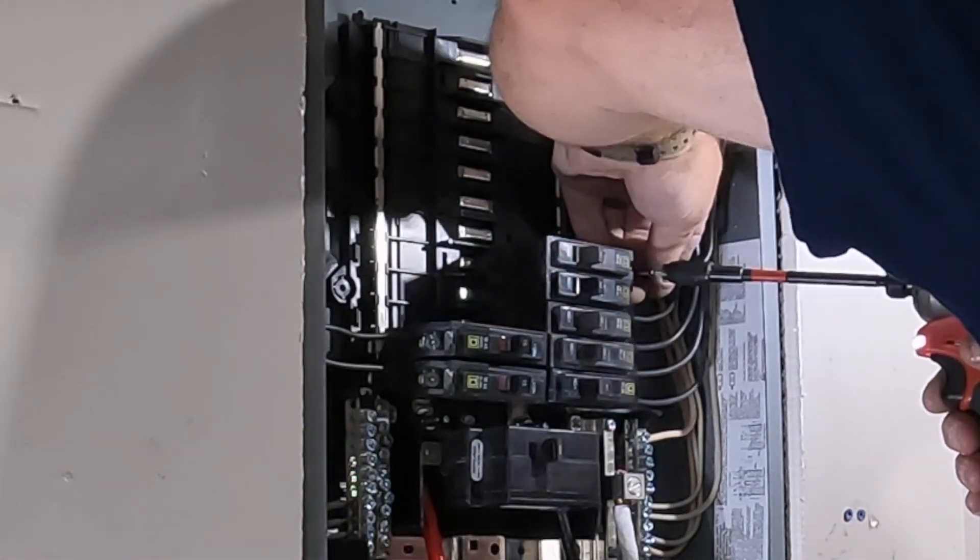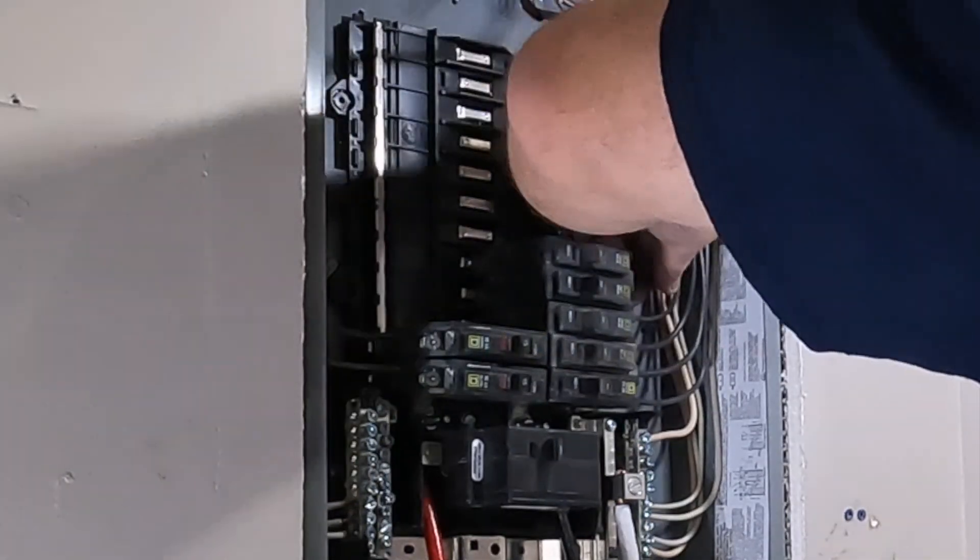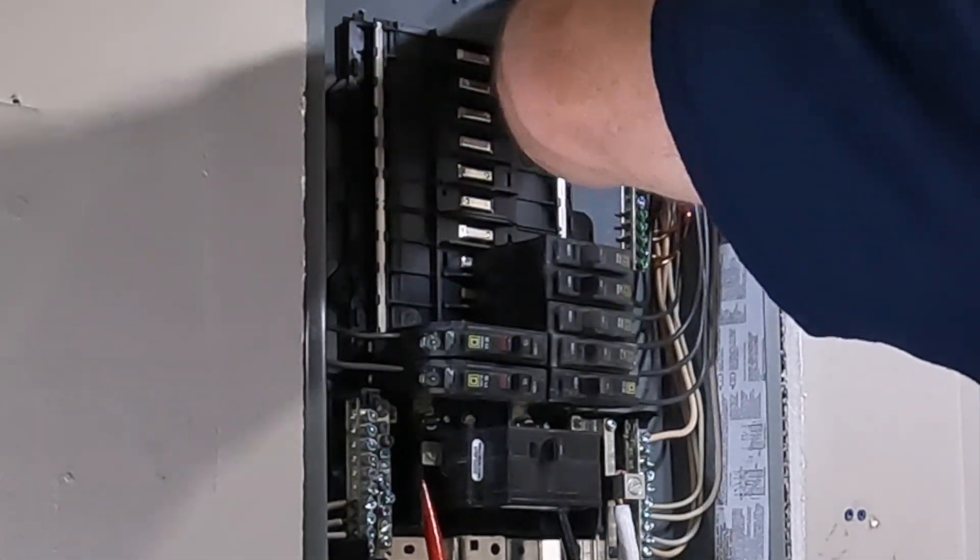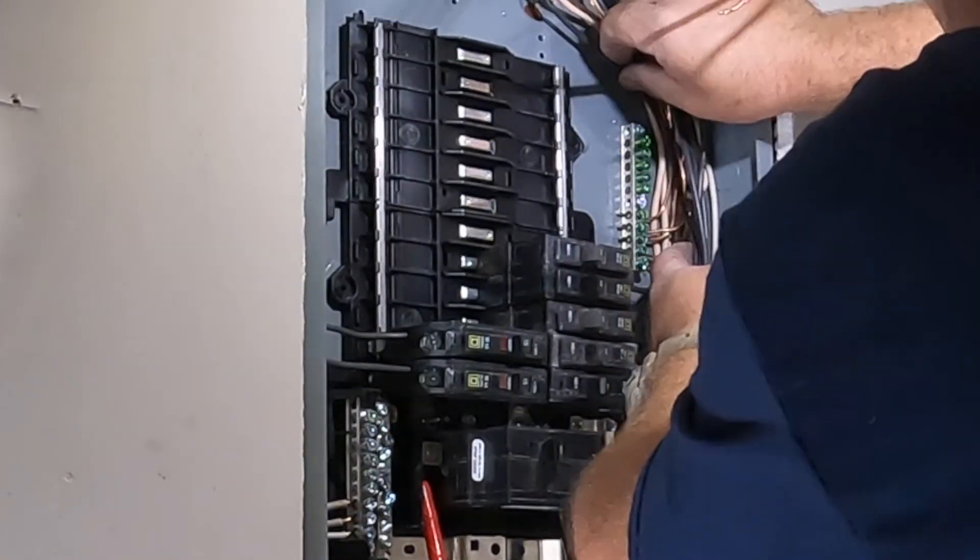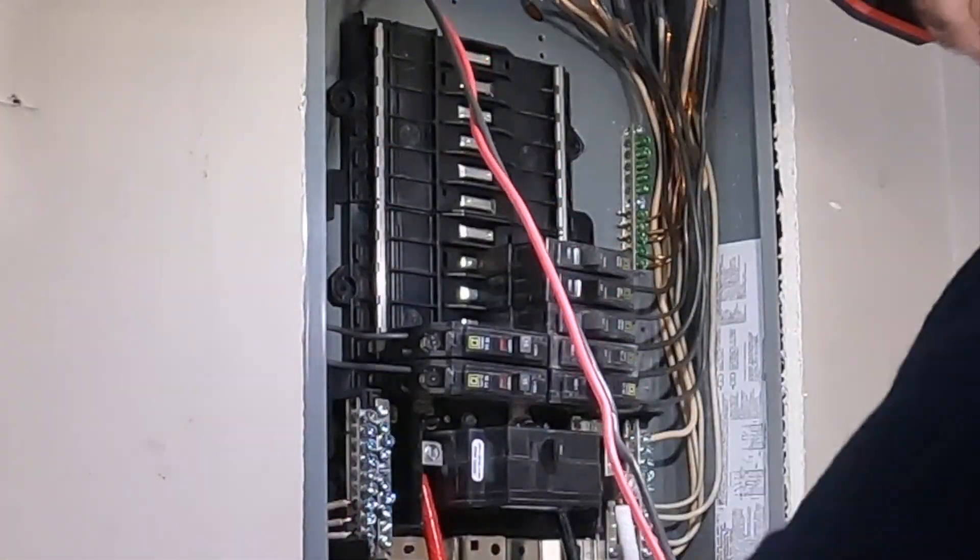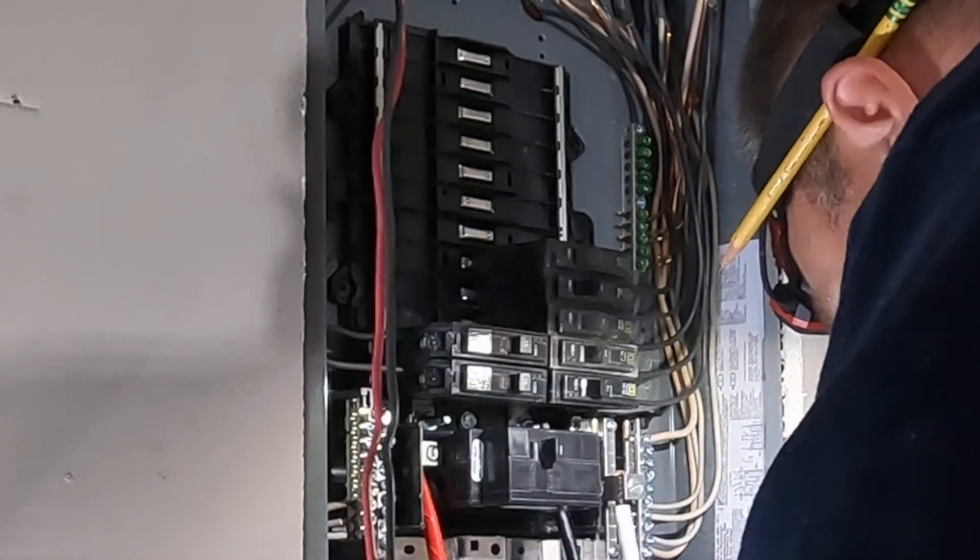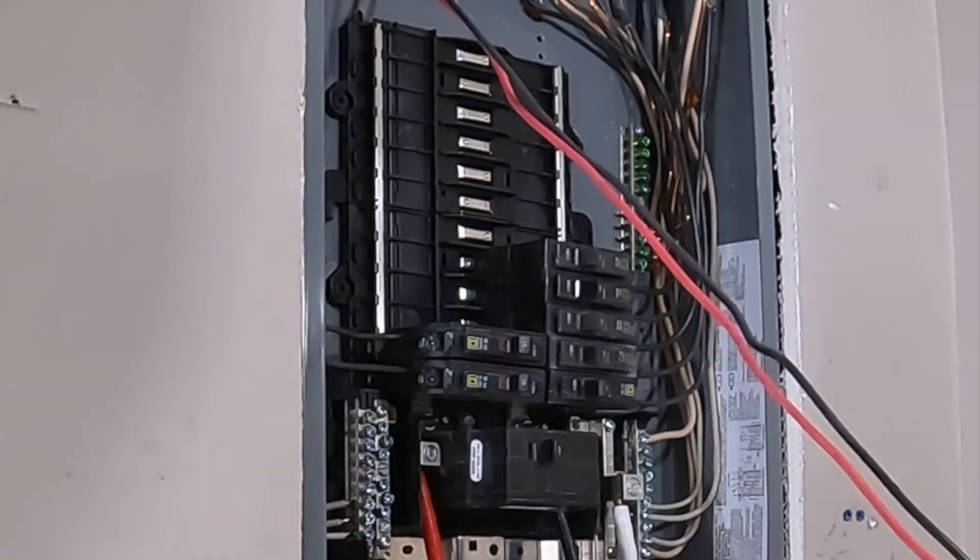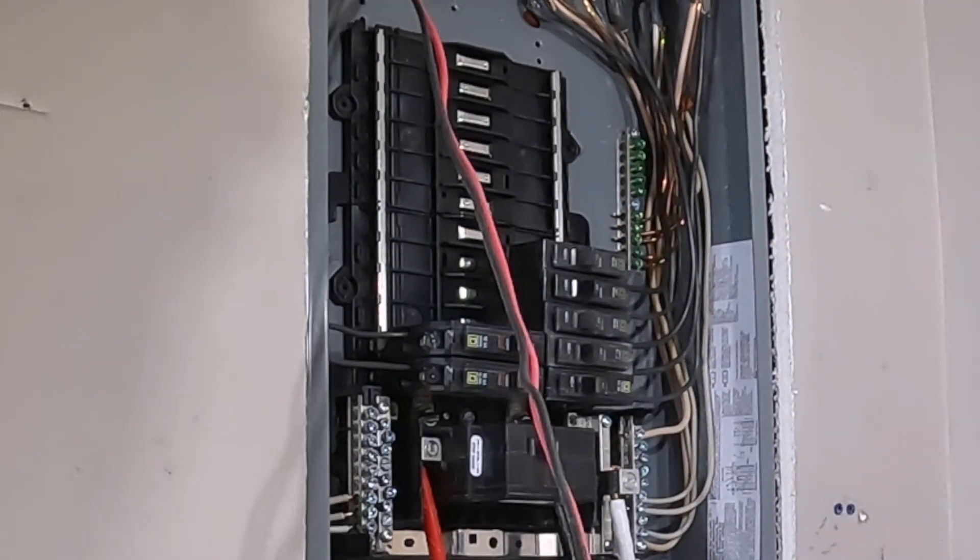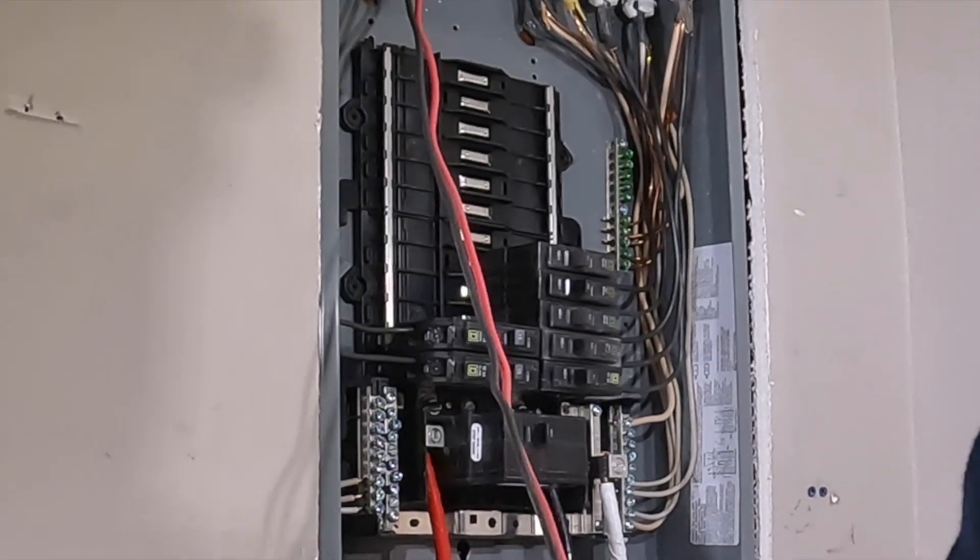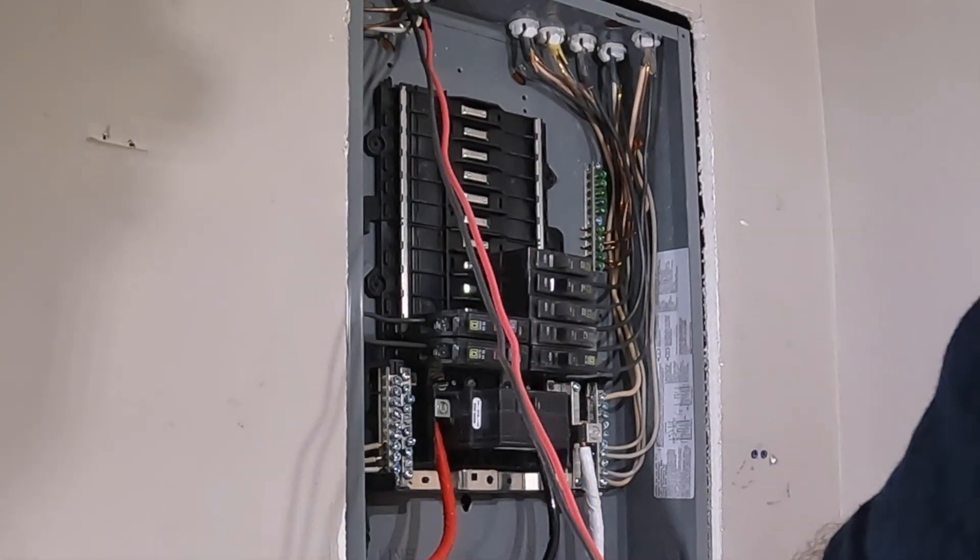So I think there's maybe, let's see, there's one, two, three, four, five, six, seven circuits here. And there was one set of, one branch circuit, set of wires, a multi-wire branch circuit that was disconnected previously. And I think that was for an old electric heater or maybe a stove. But they no longer use those wires - right in front of you there, the red and the black, that's number 10. Might have even been for an old electric water heater and now there's natural gas. I forget what the story was with that.